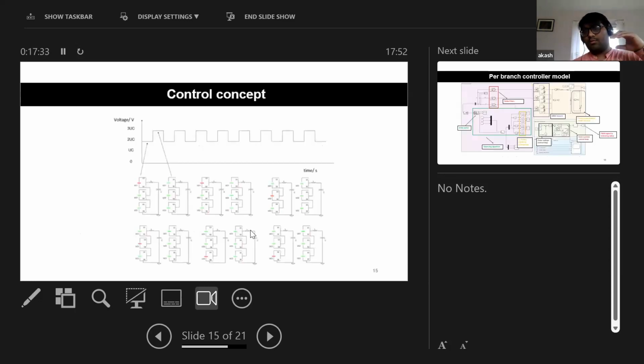Now the values you get out of the two-loop controller go into a balancing algorithm. One of the issues with the multi-level design is the submodules within the branch need to be balanced out so that one submodule doesn't overproduce current, otherwise you need to oversize your switches even more.